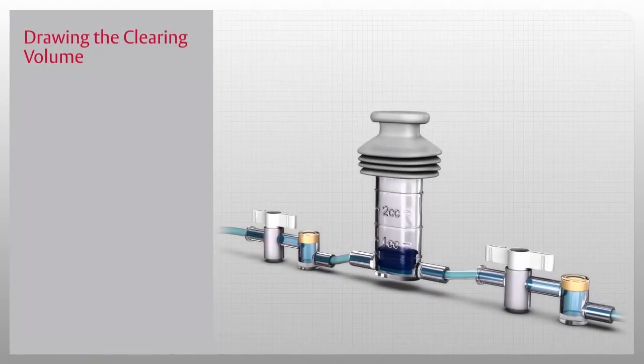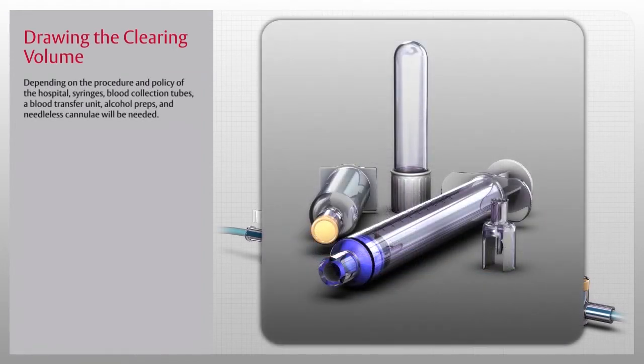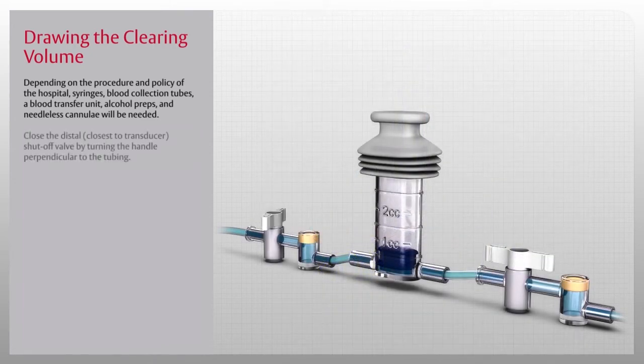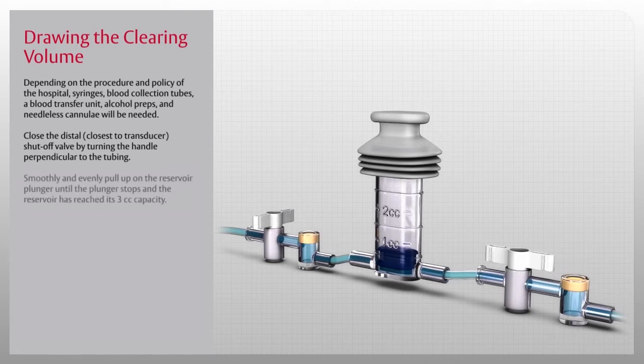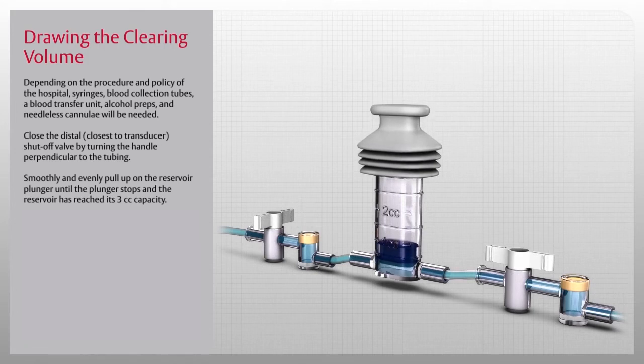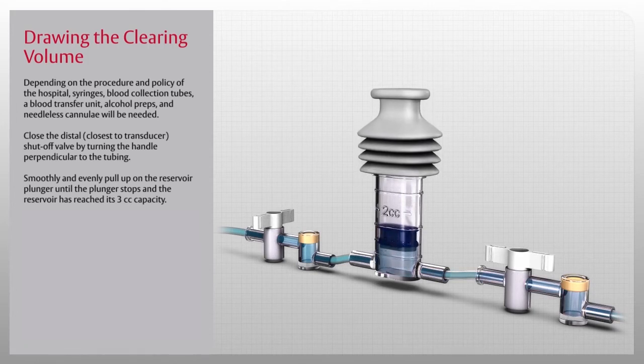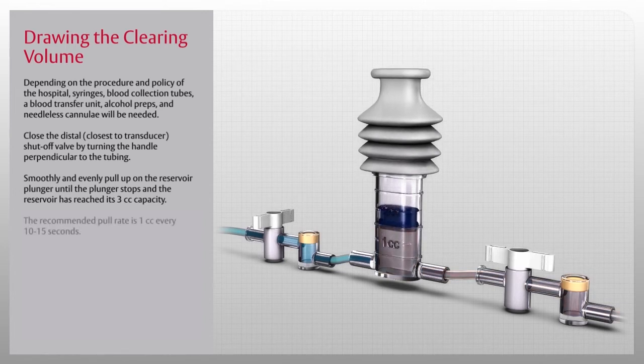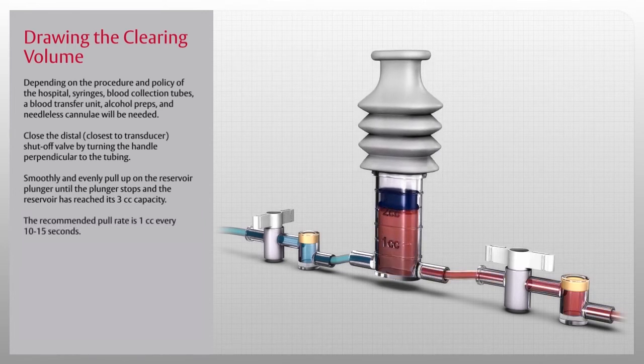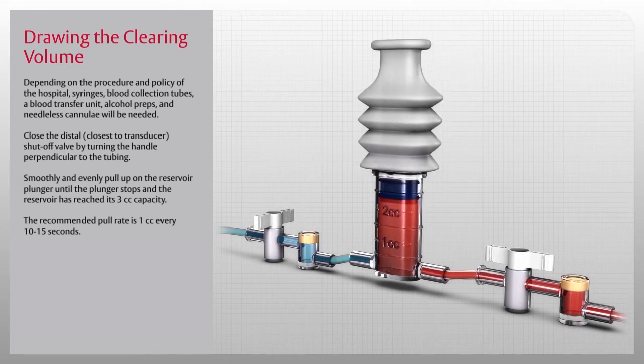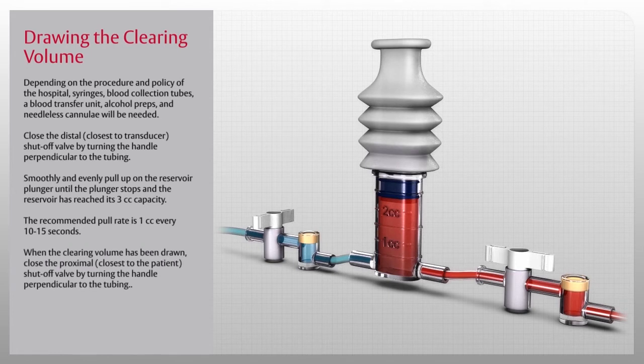Once the system is primed, you are now ready to draw the clearing volume. Note, depending on the procedure and policy of the hospital, syringes, blood collection tubes, a blood transfer unit, alcohol preps, and needleless cannula will be needed. First, close the distal shutoff valve by turning the handle perpendicular to the tubing. Now, smoothly and evenly pull up on the reservoir plunger until the plunger stops and the reservoir has reached its 3 cc capacity. The recommended pull rate is 1 cc every 10 to 15 seconds. When the volume has been drawn, close the proximal shutoff valve by turning the handle perpendicular to the tubing.